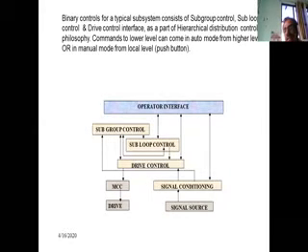No. It is not safe to run the turbine. Then in this case, it will give a signal to the subgroup control, saying I am not able to generate the lube oil. Then subgroup control will take care of that, and it will give a trip signal to the turbine.